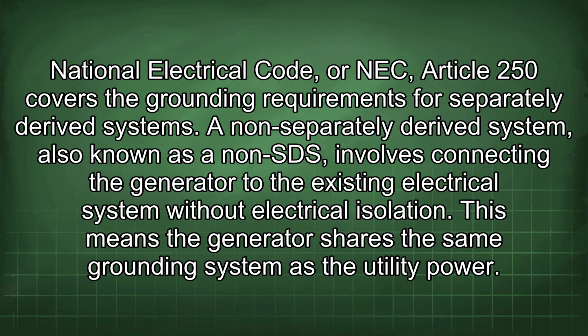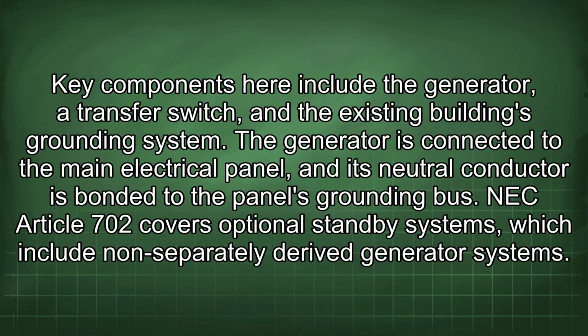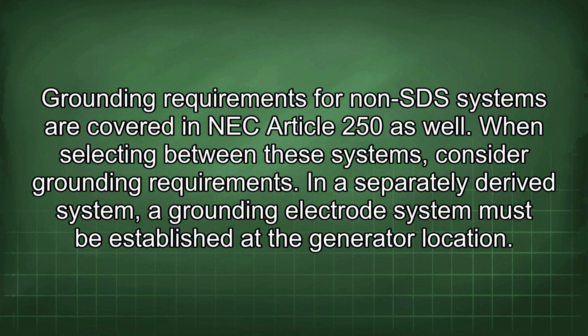A non-separately derived system, also known as a non-SDS, involves connecting the generator to the existing electrical system without electrical isolation. This means the generator shares the same grounding system as the utility power. Key components here include the generator, a transfer switch, and the existing building's grounding system. The generator is connected to the main electrical panel and its neutral conductor is bonded to the panel's grounding bus. NEC Article 702 covers optional standby systems, which include non-separately derived generator systems. Grounding requirements for non-SDS systems are covered in NEC Article 250 as well.